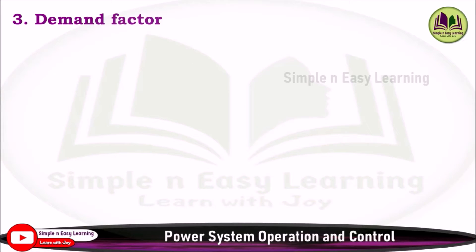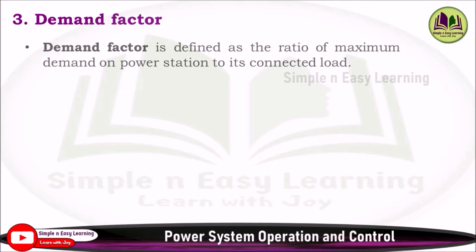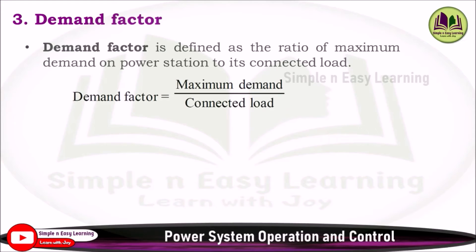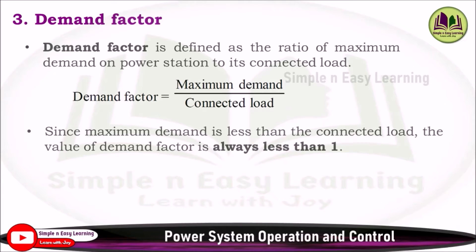Third: demand factor. Demand factor is defined as the ratio of maximum demand on the power station to its connected load. The formula is: Demand Factor = Maximum Demand / Connected Load. Since maximum demand is always less than connected load, the value of demand factor is always less than 1.